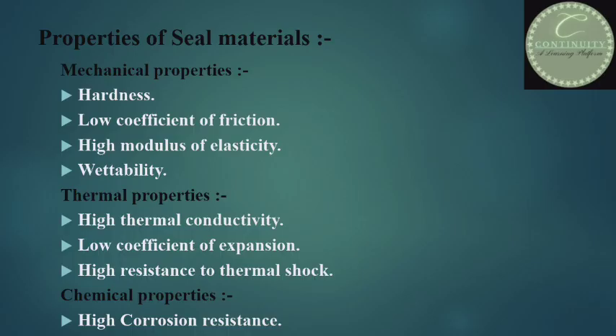Now, the properties of seal materials — what should be the properties of materials used for making a mechanical seal? Mechanical properties: hardness, low coefficient of friction, high modulus of elasticity, and wettability. Thermal properties: high thermal conductivity, low coefficient of expansion, and high resistance to thermal shock. Chemical properties: high corrosion resistance.